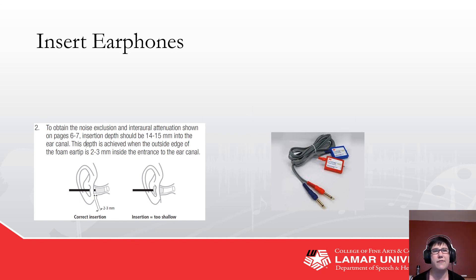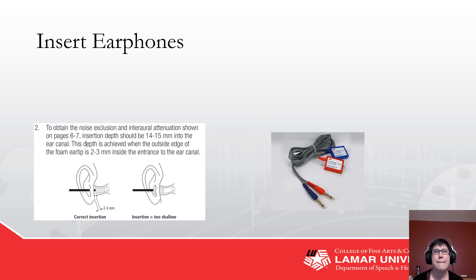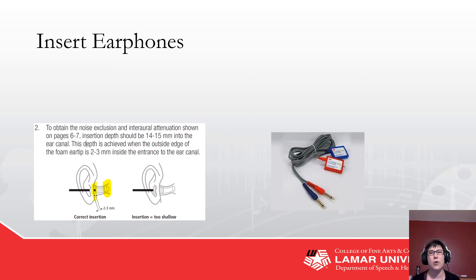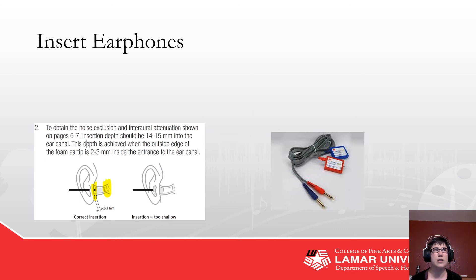Insert earphones are probably my favorite. They can be a little uncomfortable, but they have the best noise exclusion and the best interaural attenuation. However, they're tricky — if you do not get them in and they're not countersunk, as discussed in the transducers video, you're not getting the results you think you are. Sound is pressure, and these are calibrated to assume there is very little residual ear canal volume between the tip and the tympanic membrane.